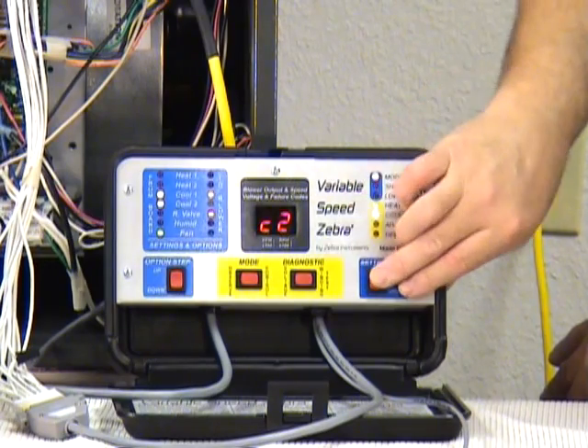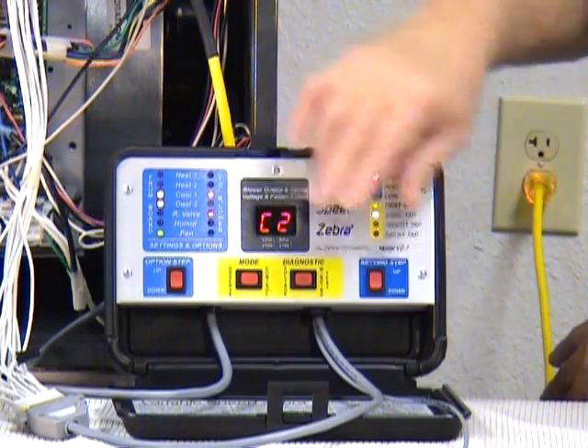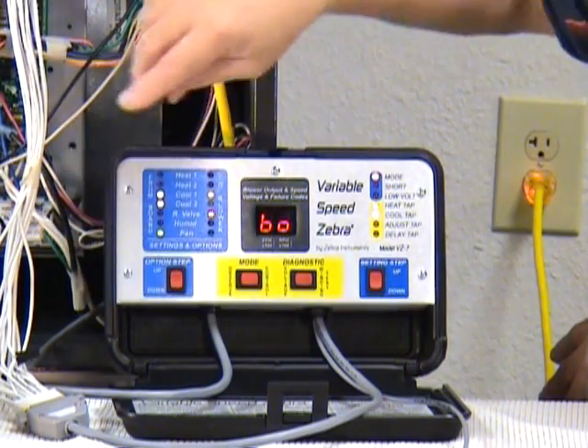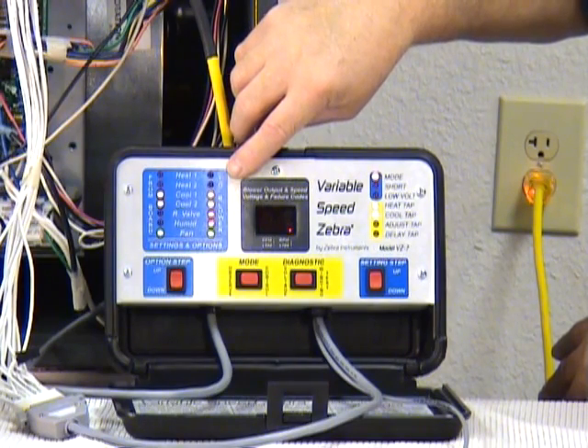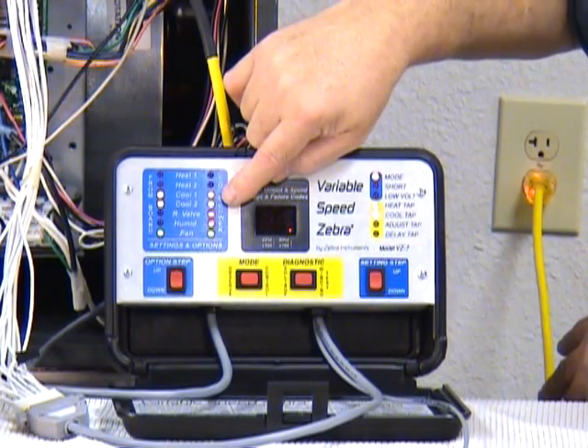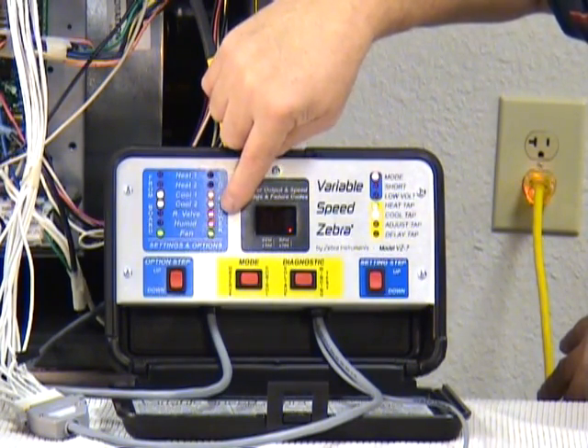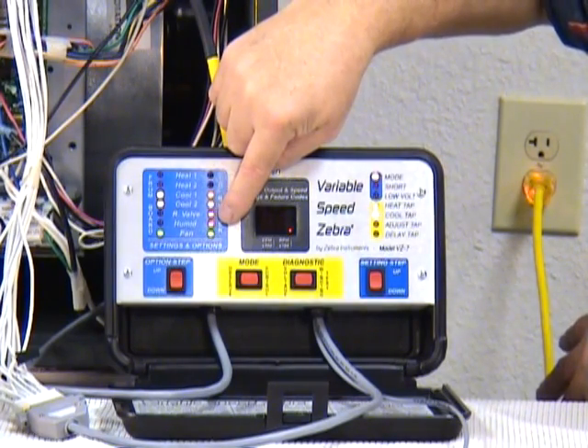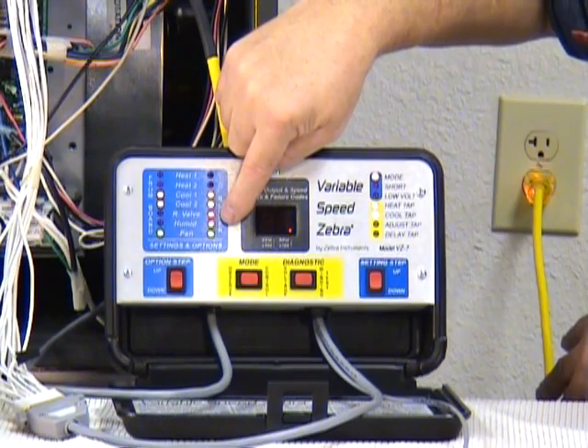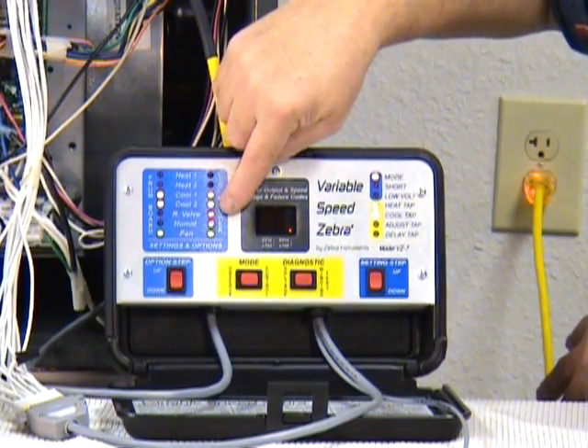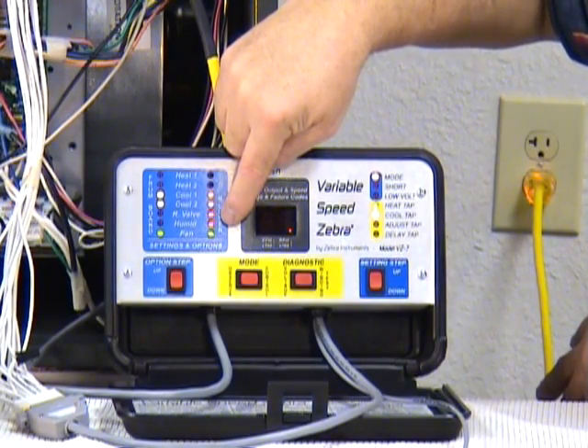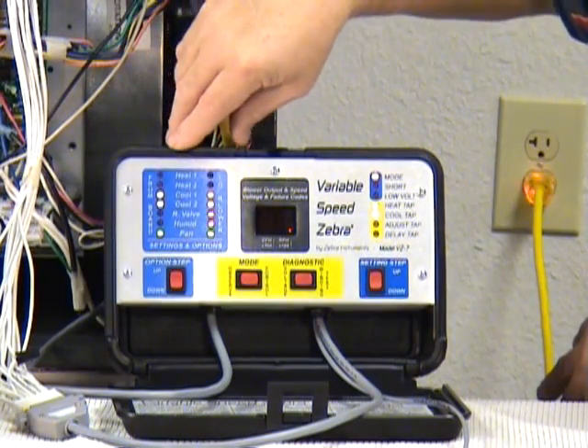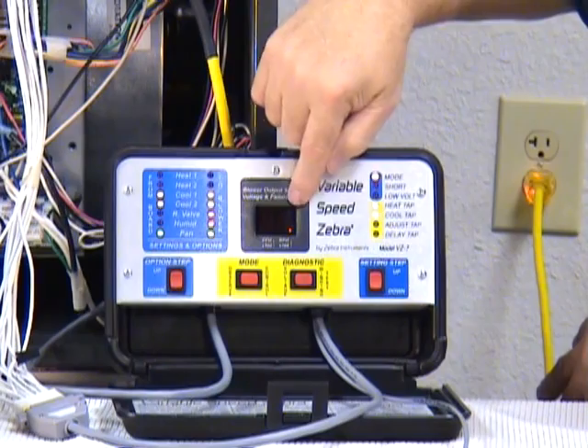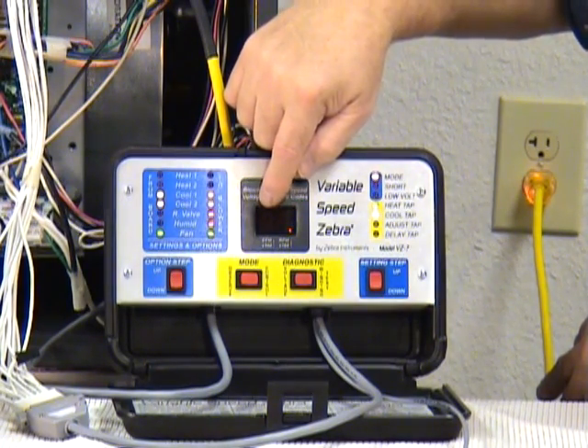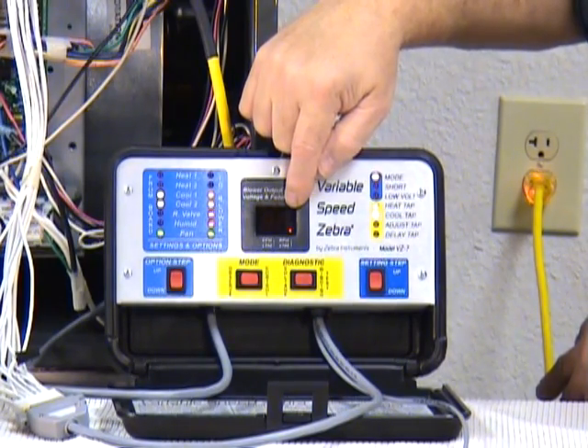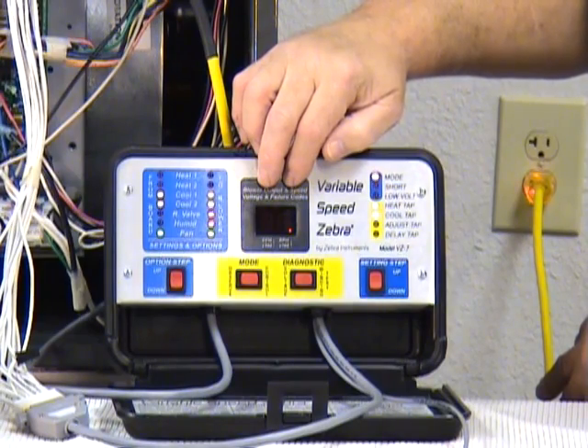You use the setting step switch and the option step switch to select which lines you want to activate going to your motor. In this case, we've activated high-speed cooling and low-speed cooling together. The reversing valve is activated, so it's in heat pump mode, and the humidistat is satisfied, which of course in reality this would never happen. You wouldn't be running in heating and using a humidistat to remove humidity from your air. And the fan line is active, so it's on a system that uses the fan line, and of course the vast majority of them do. Normally you'd be receiving feedback from your motor right now about the CFM and the RPM that the motor's running at, but we shut it off because of the noise that the fan generates when it's in those higher speeds.